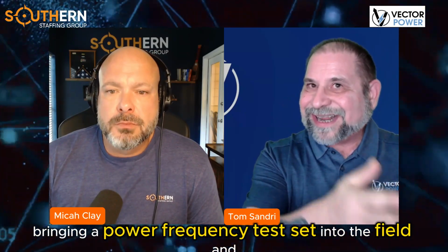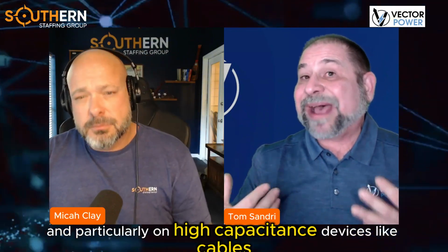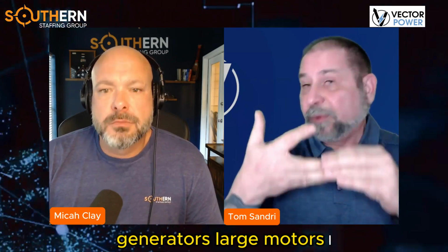You'll still basically get what you're looking for, though the question remains about quality or any issues. If you're a purist with the budget and environment to support one of these dedicated testing systems, more power to you. I'm all for testing at 60 hertz. In a perfect world, we would never have used DC, VLF, or any alternative frequencies. But the fact is, through time and history, bringing a power frequency test set into the field, particularly onto high-capacitive devices like cables, generators, and large motors, just isn't practical or cost-effective for a field environment.